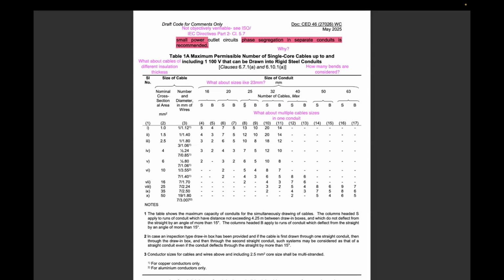One circuit may be run in 1.5 square millimeter, one circuit may be run in 2.5 square millimeter. This table does not provide any information on that. It only tells us how much you can have of one size. Secondly, 16, 20, 25, 32, 40, 50. These are sizes that are available. There are also other sizes that are available. Sometimes they're 23 millimeters. What about those?